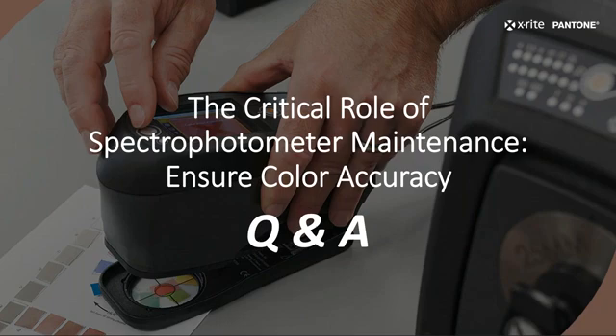The distinction comes in that, again, let's assume that the sphere inside my instrument is getting dirtier and dirtier. NetProfiler will keep correcting that, right? But it's correcting or adjusting for the fact that the sphere itself is starting to go out and cause the device natively to measure incorrectly. We can keep correcting those errors to a certain degree. There are times when, if a device is bad enough, NetProfiler would actually fail. But let's assume it keeps doing that. Then when you send your device in for annual certification, when we certify an instrument, we also clean it. It may not pass, and if it doesn't, there may be some adjustments needed, or like I said, if some component requires repair or replacement, that can be done as well to make sure the instrument is back to measuring as good as it possibly can.